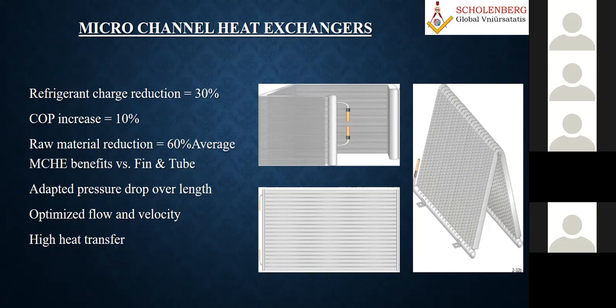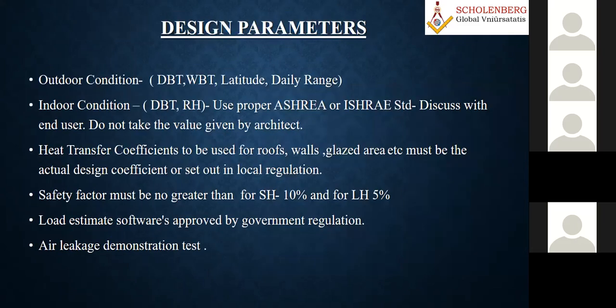And each refrigerant has different kinds of properties: different boiling point, different viscosity, different density, kinematic viscosity, all these. Those are the refrigerant properties, which normally the manufacturers decide. But the heat exchanger part, maybe you may say, sir, we are not going to select this type of thing. Maybe when you are going to design your cooling coils, your AHUs, you can always insist on this type of micro-channel heat exchanger and put it in your specification. That will definitely help you.